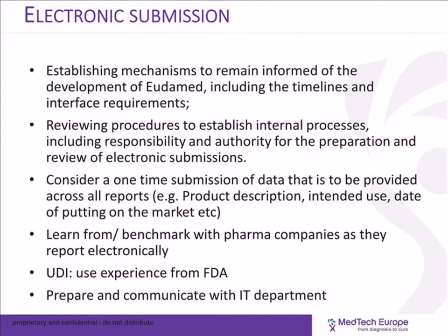And finally, this is my last slide in this training from the post-market working group, the electronic submission. Big change for us. This is EUDAMED. I'm sure that you are very familiar with the various activities ongoing with EUDAMED. In terms of PMS, we need to establish the mechanism to feed EUDAMED to make sure that we include the timeline and the interface.